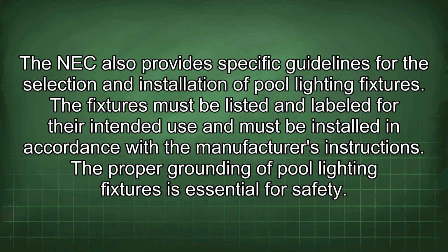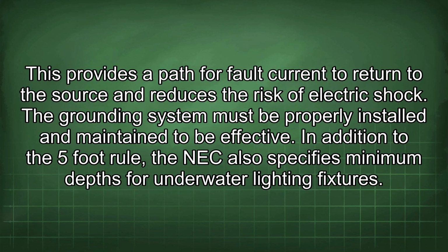The NEC also provides specific guidelines for the selection and installation of pool lighting fixtures. The fixtures must be listed and labeled for their intended use and must be installed in accordance with the manufacturer's instructions. Proper grounding of pool lighting fixtures is essential for safety, providing a path for fault current to return to the source and reducing the risk of electric shock. The grounding system must be properly installed and maintained to be effective.